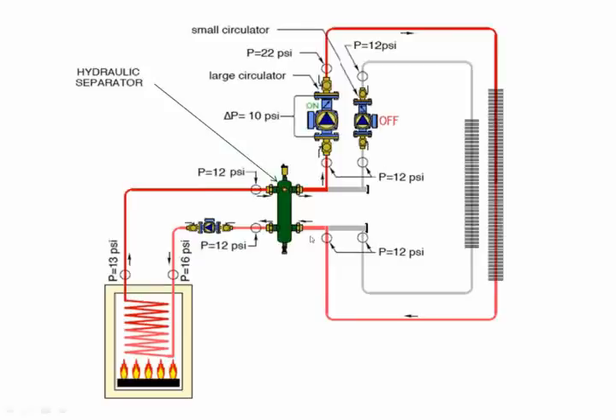So how do we fix that? Well, we do a couple things. We put a hydraulic separator in our line. By doing that, we create a bypass, if you will, or shortcut for our secondary pumps to send flow. Okay? But now we've cut off flow over here, so we need to put on a pump, a very small pump at that, because it's only worried about sending flow here. And the last thing is we want to make sure our headers are designed for the velocity to be more or less under 4 feet per second. If they're a very long length of pipe, maybe 2 feet per second, short length of pipe, maybe 6 feet per second. But use 4 feet per second as a rule of thumb.